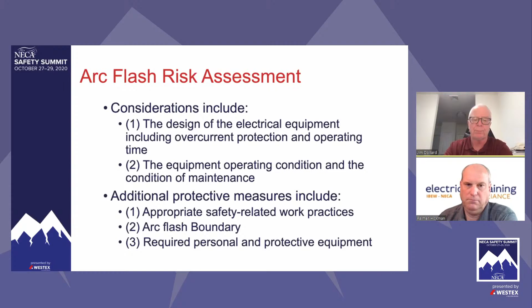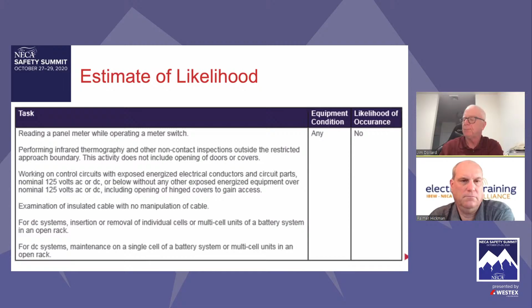And I like to take a look at that second one down. It says performing infrared thermography and other non-contact inspections outside the restricted approach boundary. And we're going to tell you on the right that that's any equipment condition. There is no likelihood of occurrence. But look at the last part of it. This activity does not include opening of doors or covers. Because when we open a bolted cover, Palmer, we have an arc flash likelihood, right? Absolutely. Okay.